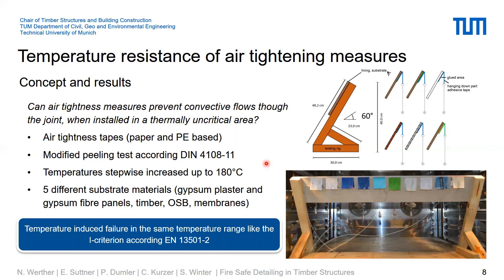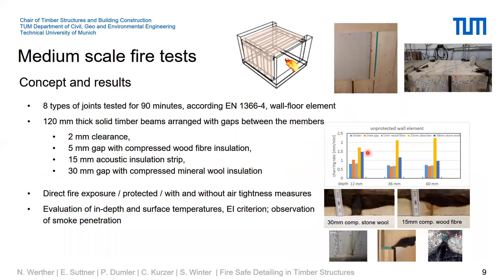Briefly, the results show that the temperature-induced failure is more or less in the same range as the insulation criteria according to the European classification system — that means roughly in the range of 180 degrees Celsius temperature increase.